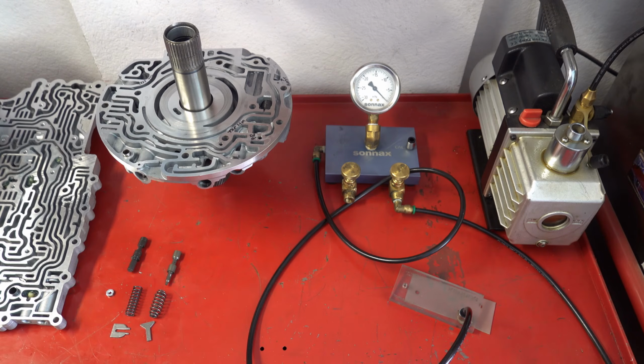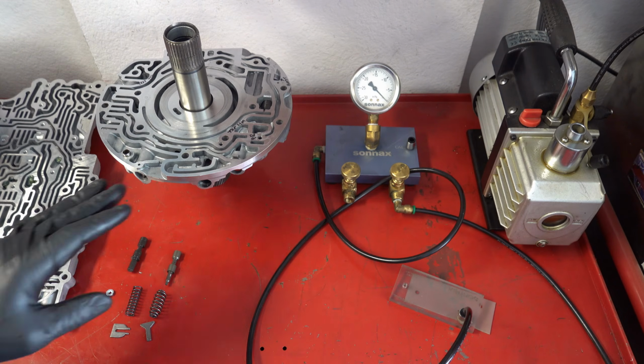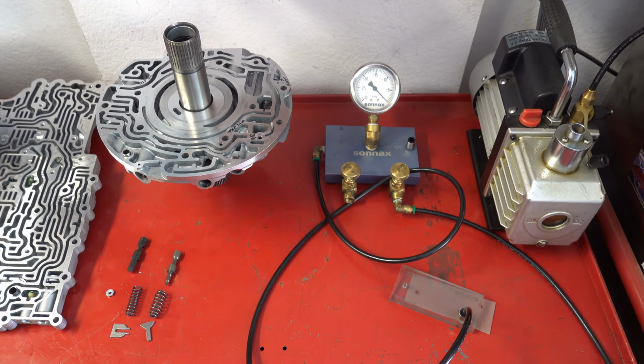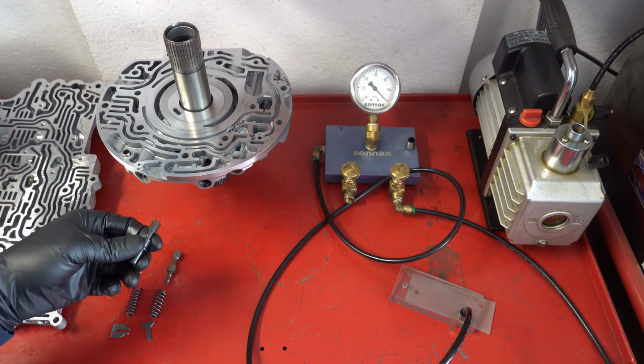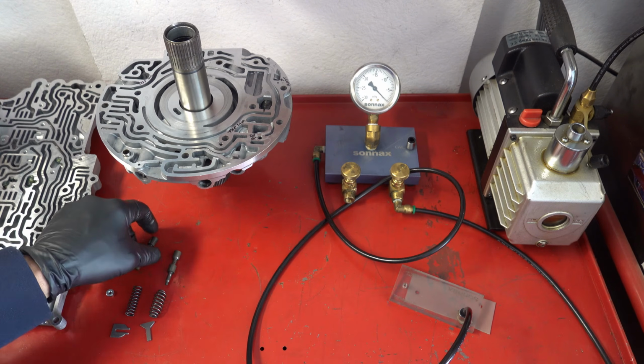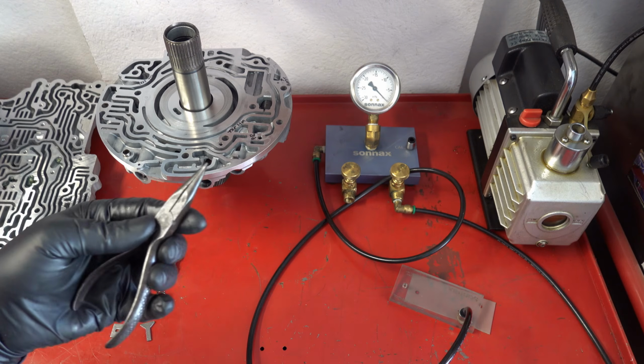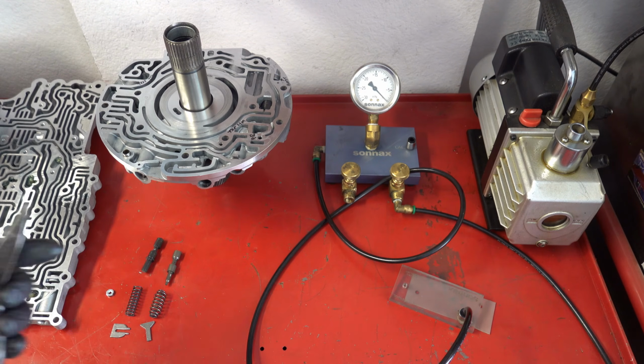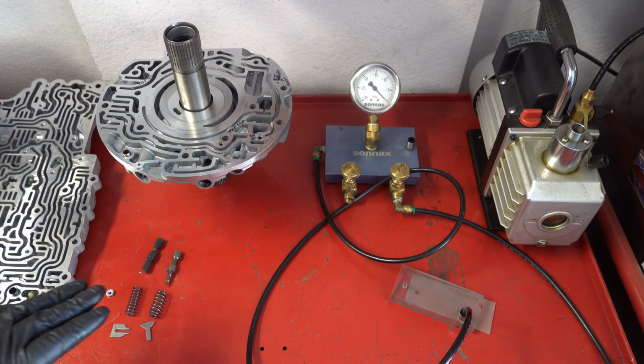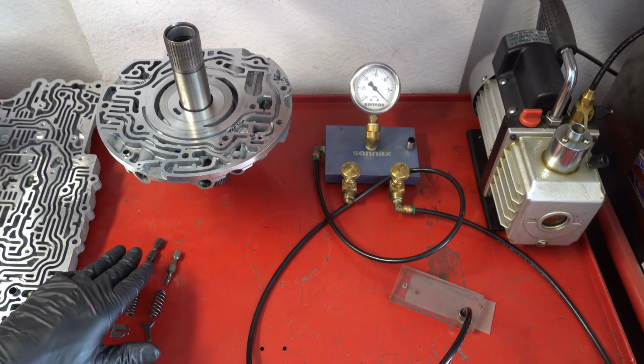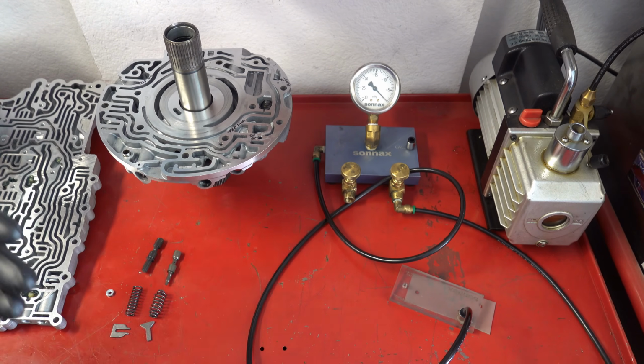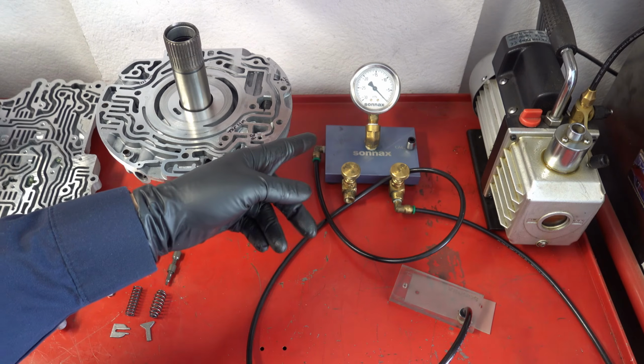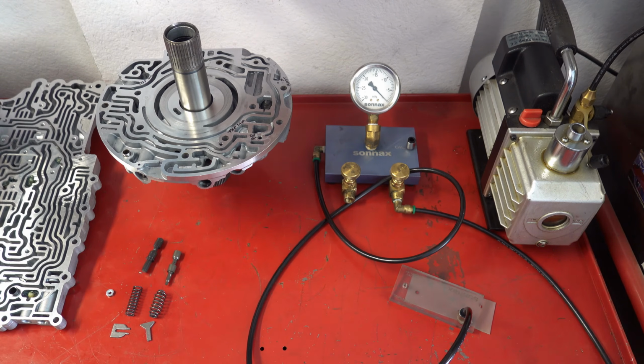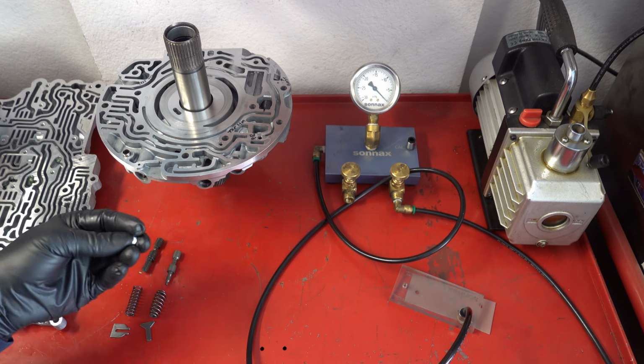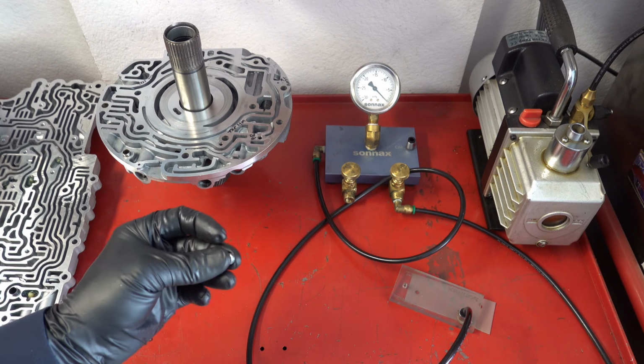So when we have the tester and the block over, we're going to need to take a small pair of needle nose pliers and hold the valve in place, because when we go to test, the vacuum will actually suck this valve all the way inboard. So you'll see vacuum for a split second on the gauge, and then it'll drop to 0. You also want to have your little 125 thou thick nut handy.